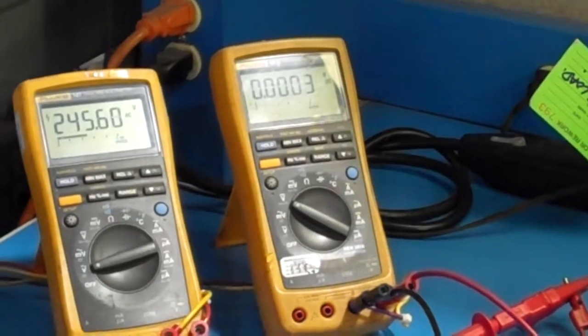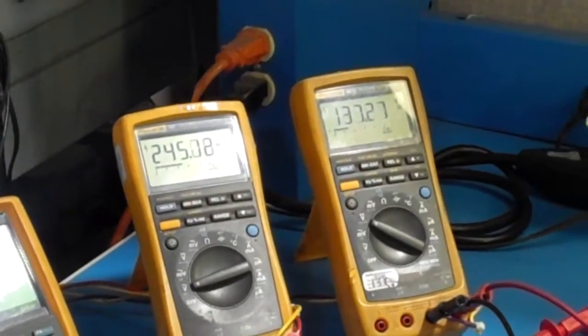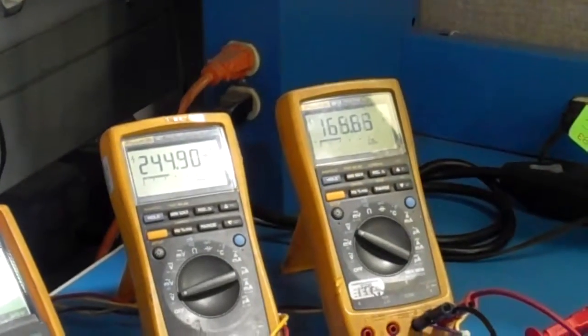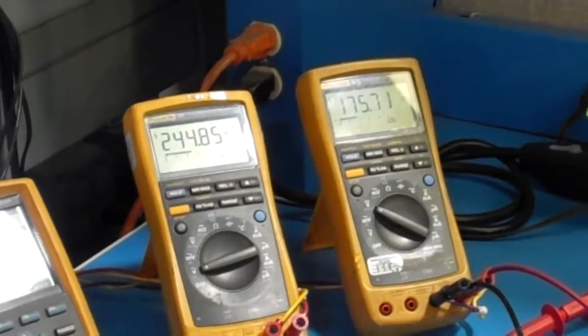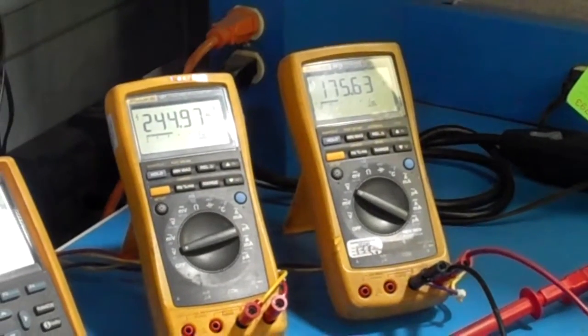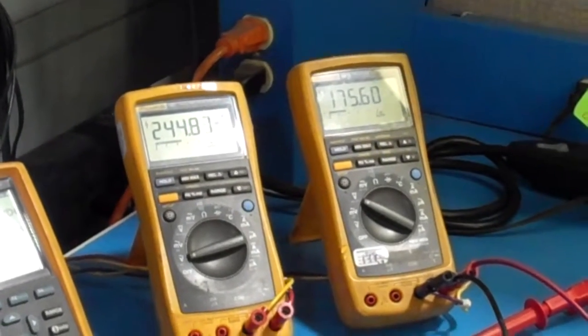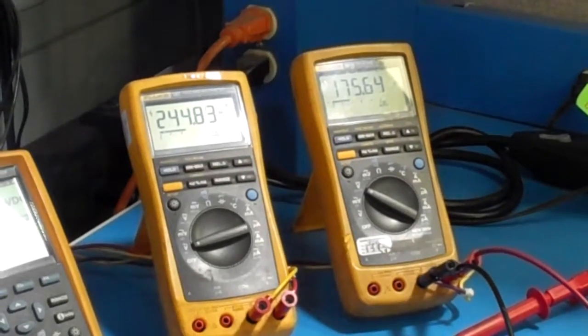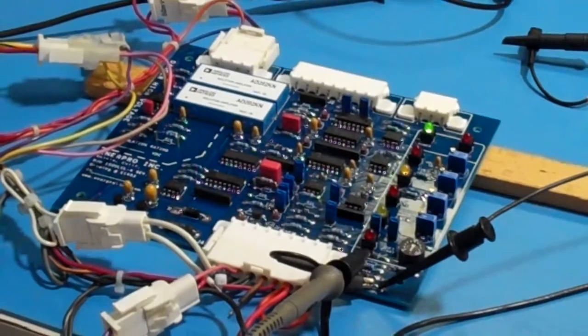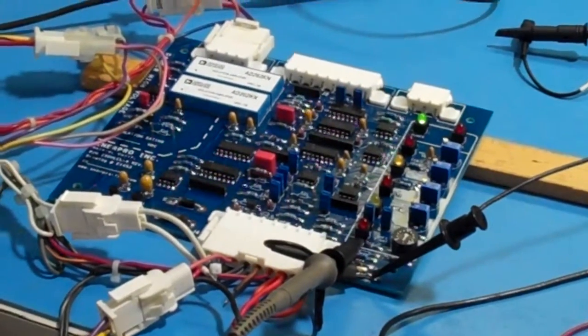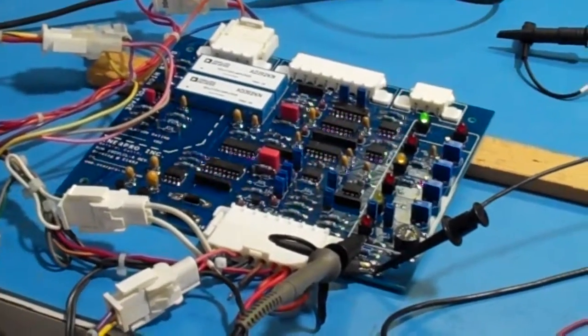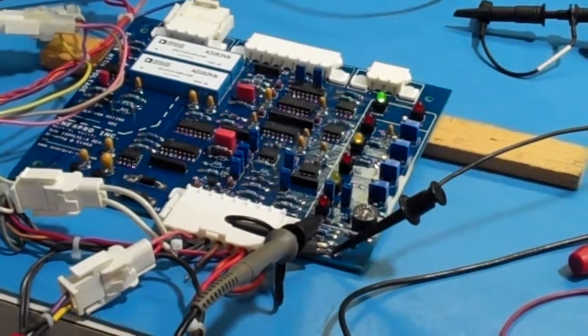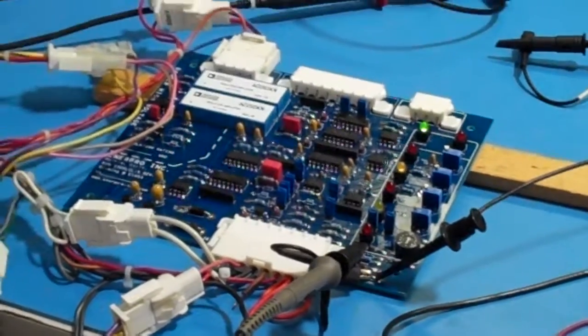is 0. I'm going to ask Tony to soft enable the board, and we'll notice that the output will start increasing to a previously set value of 175 volts that was chosen randomly. 175 volts DC. At that point we notice that the voltage is limited because we have used the voltage limit potentiometer to adjust that to 175, and the red soft start LED is off.